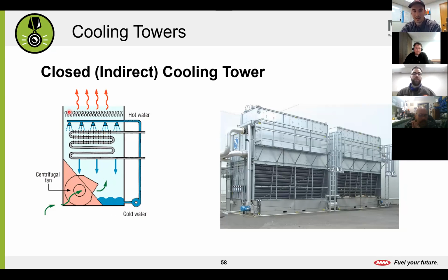With that, you'll see mist eliminators. A lot of that is so we're not wasting a lot of water, because when the cooling tower sump pump is running and pumping water down over our condenser water, a lot of that is going to want to start evaporating. And that's water you have to make up, you have to fill, and you've got to pay to refill it. So you'll have things like mist eliminators, as we call them, where it captures that mist, condenses it, drops it back down to the sump, so you're not paying for that.